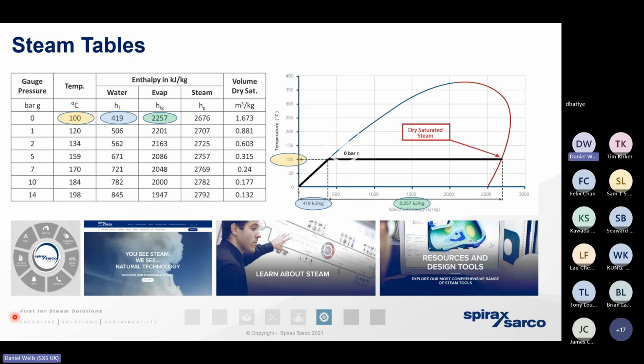And we also remember that when the steam hits the heat exchanger, it gives up its heat energy and condenses. It changes state from gas to a liquid. But when that happens, the energy demonstrated in this column is exactly the same as the energy that we put into the boiling water in order to fully evaporate and change state to give us steam as a gas. That is the energy that moves across the thermal barrier and is added to the process. In other words, we can think of that as the useful energy that the process is capable of using.